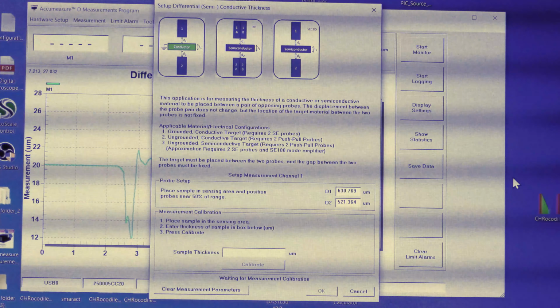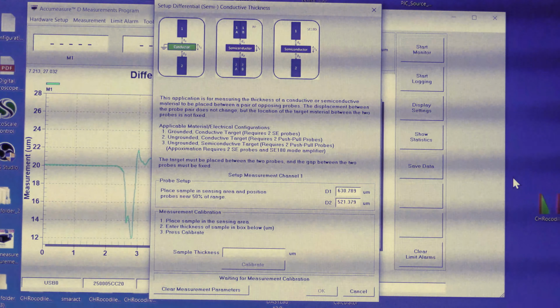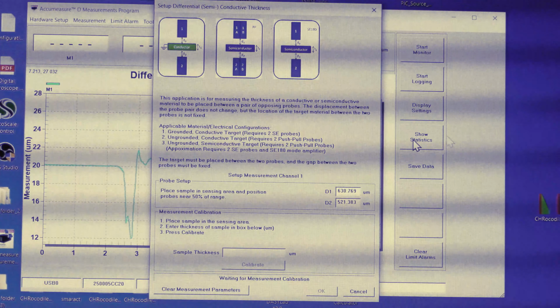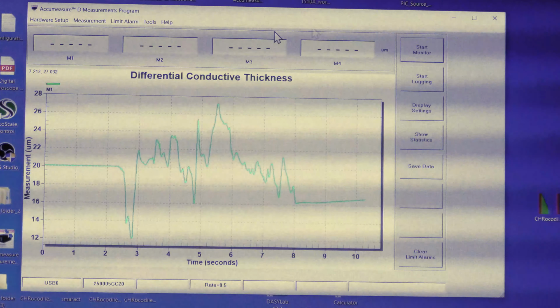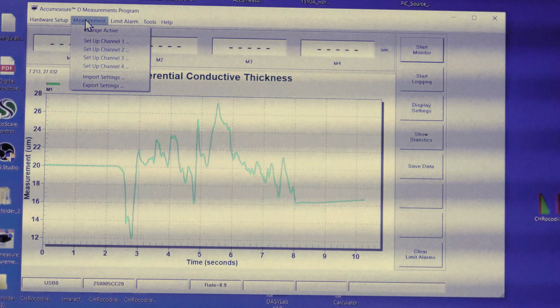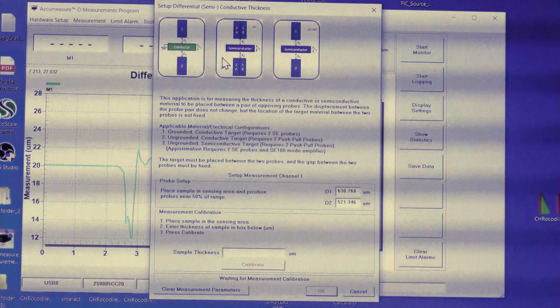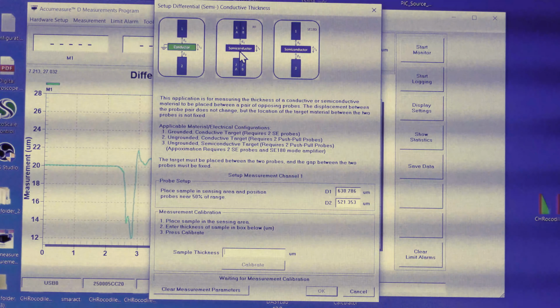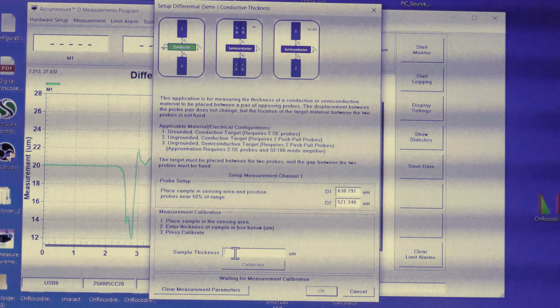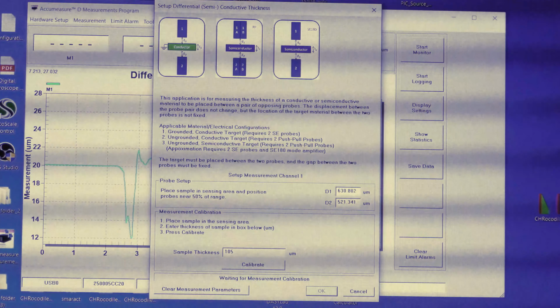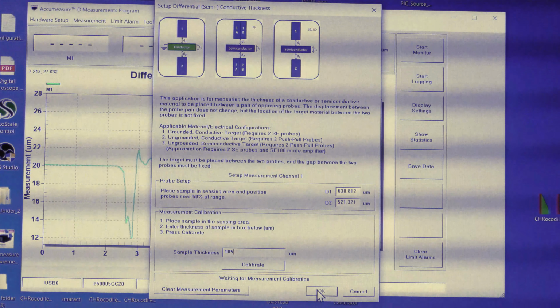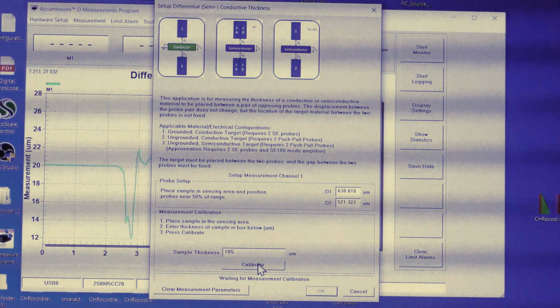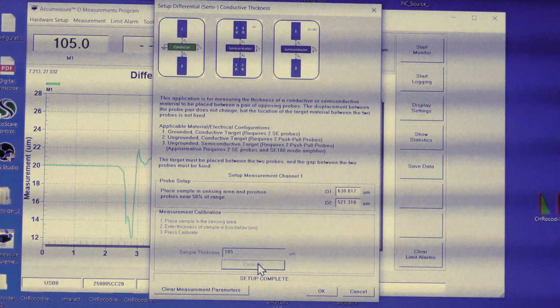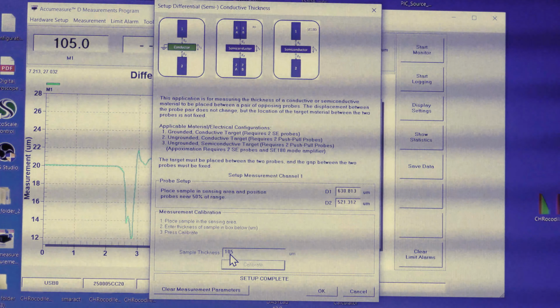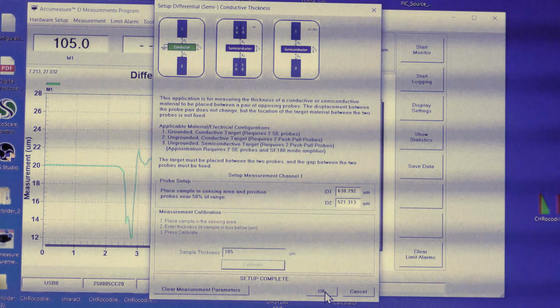All right, we've slid our test sample in, and we're going to show how we calibrate this. We've called up, under the measurement tab here, setup channel 1. We click on that. This is the situation we have here, two push-pull probes, and we're going to put our sample thickness in. So this is 105 microns thick. We simply put 105 in there. We click calibrate. So we're now calibrated to that sample, 105 microns. So I'm going to click on OK, and we're all set.